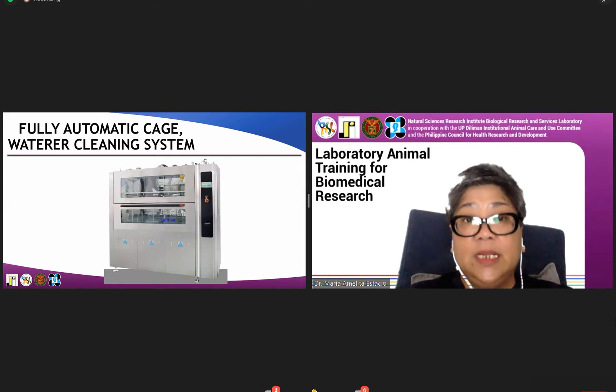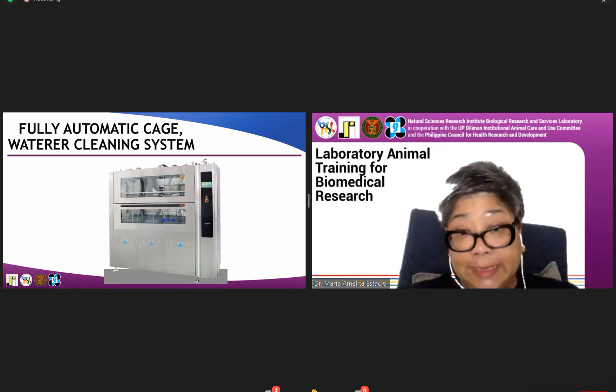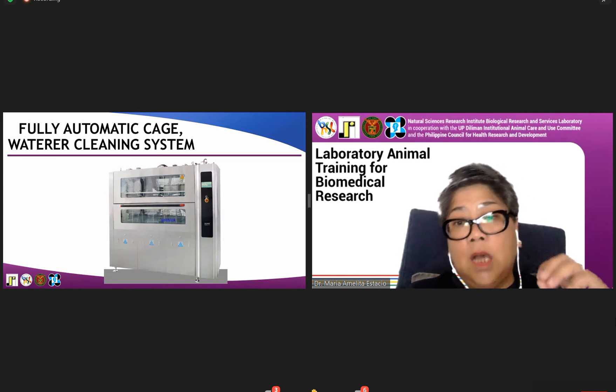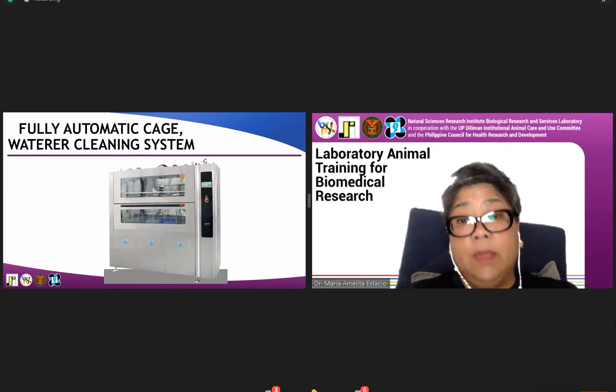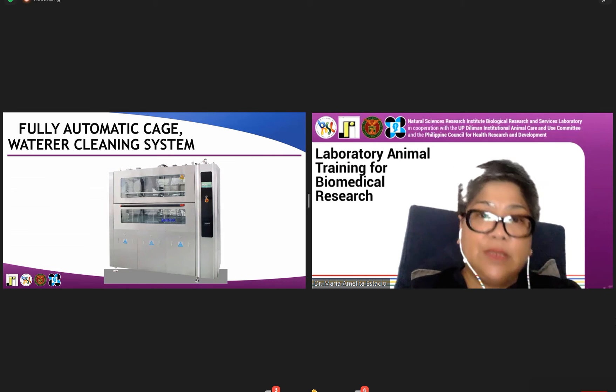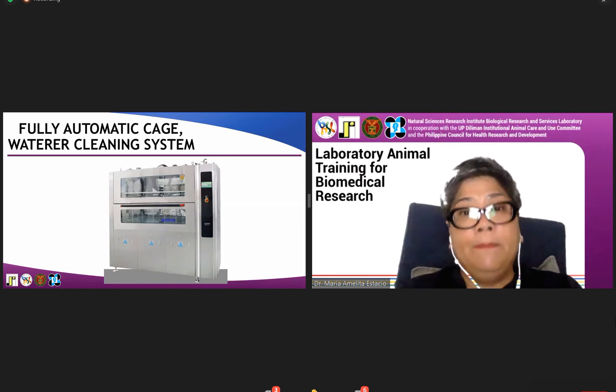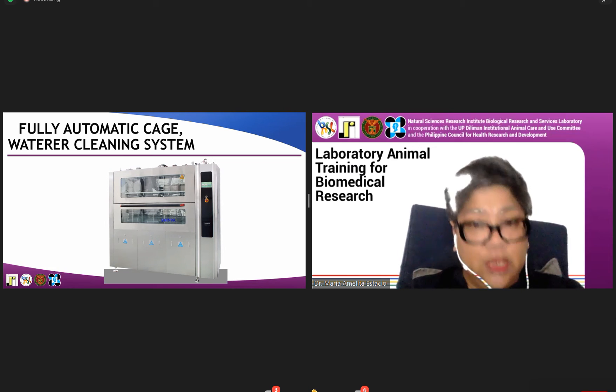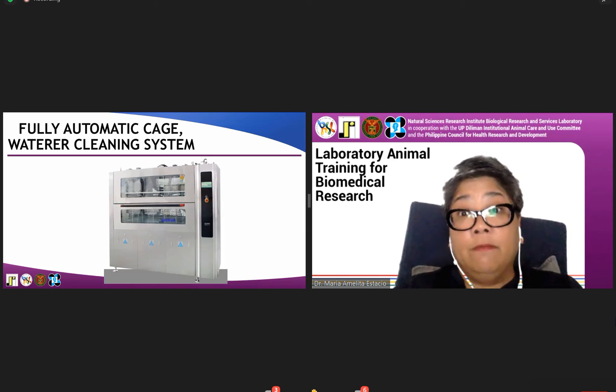For those that would be building their animal facility, there is a fully automatic cage and waterer cleaning system. This is a 40-cage, 40-waterer capacity high-pressurized hot water cage and waterer cleaning system. It can clean 40 cages in a matter of six minutes, saving you time and resources. It also ensures quality cleaning of your cages.